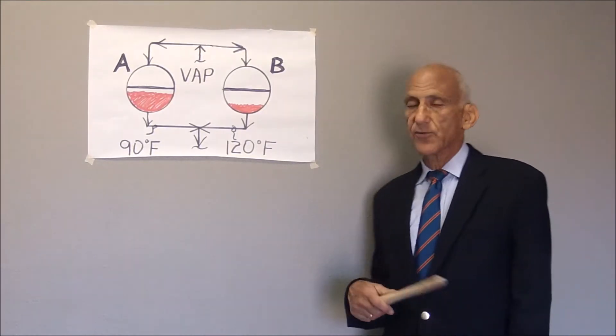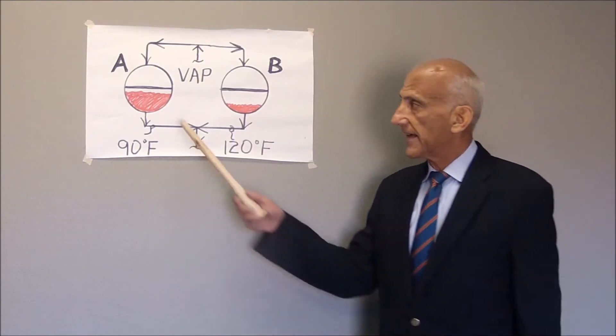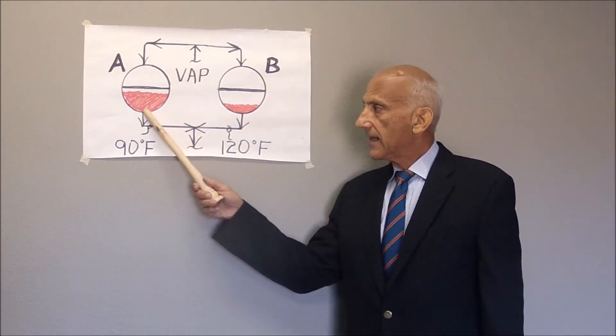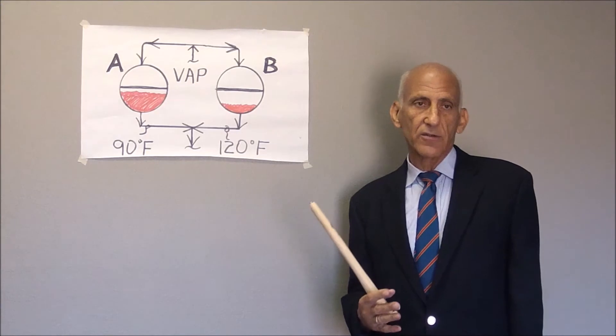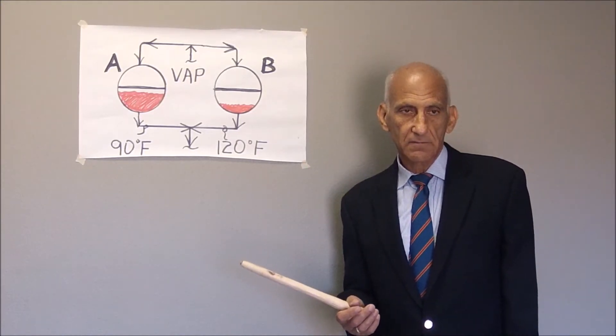But let's presume there's some obstruction in the outlet from condenser A. As the liquid flows across that obstruction, it undergoes a small pressure drop, a tenth of a pound.